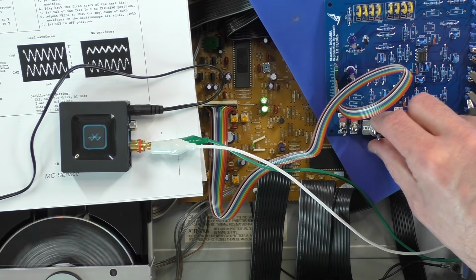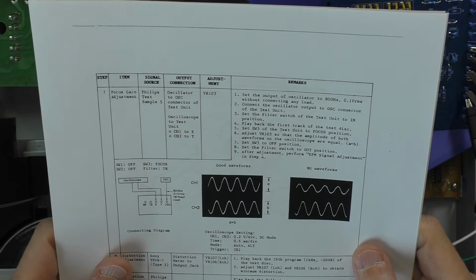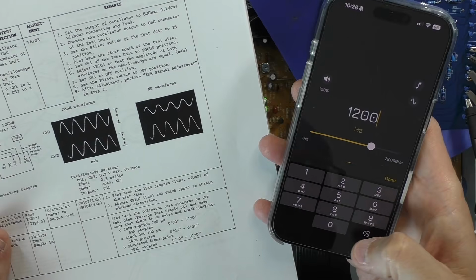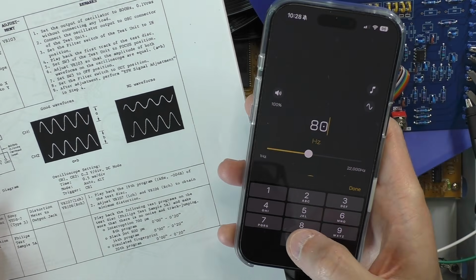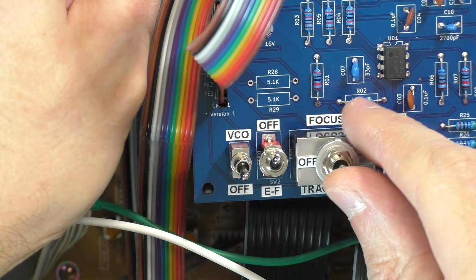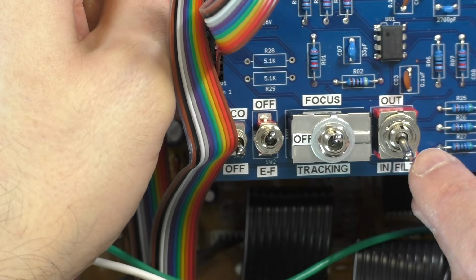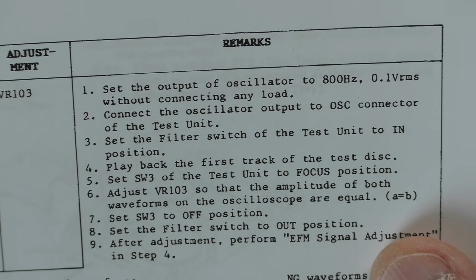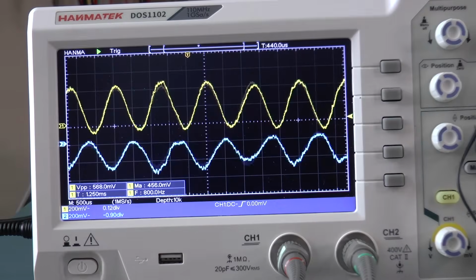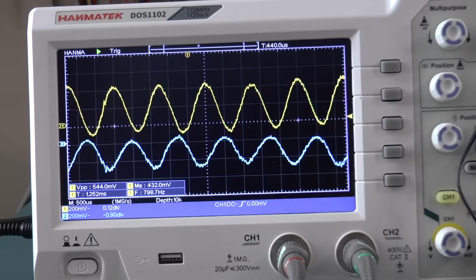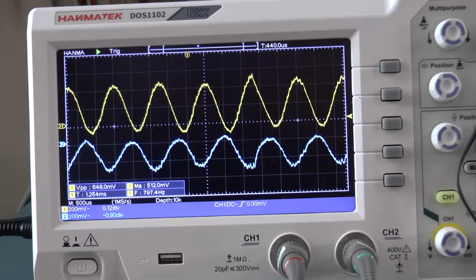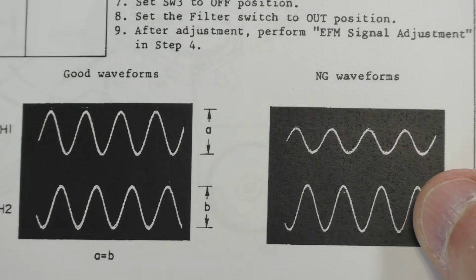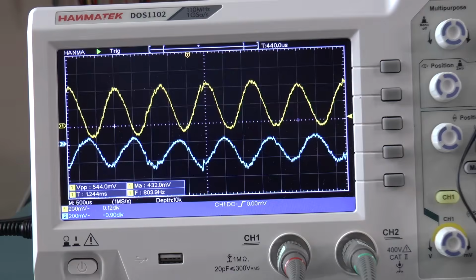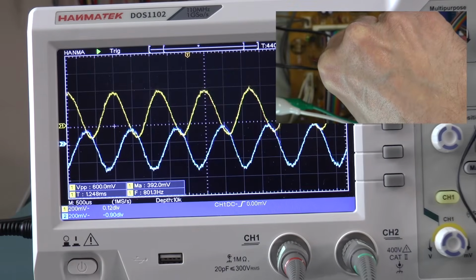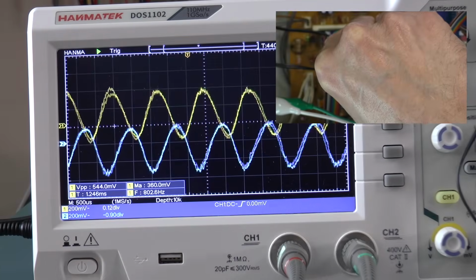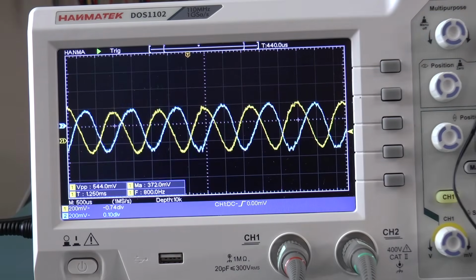Now I need to set switch 3 to the off position. And it looks like the focus gain adjustment is basically the same, only this time it needs to be 800 Hz. We move this switch to the focus position, filter switch to the in position, which it was in already, and we adjust VR103 so that the amplitude of both waveforms are equal. And this time the blue channel is significantly smaller. It kind of looks like this picture, which is not good. So let's tweak VR103. There, I would say they're now equal.